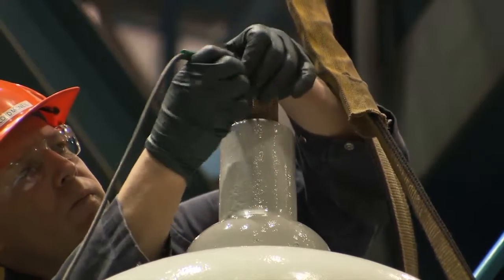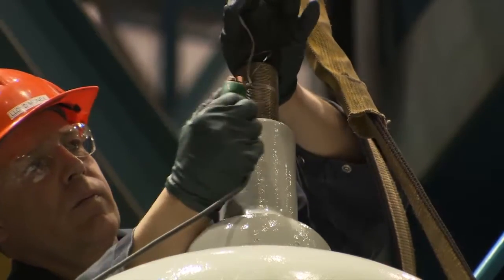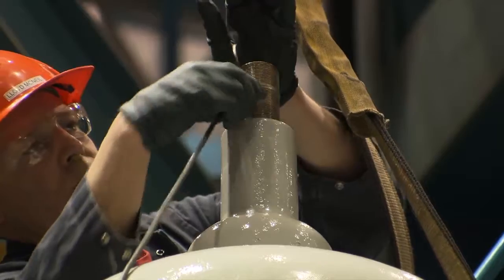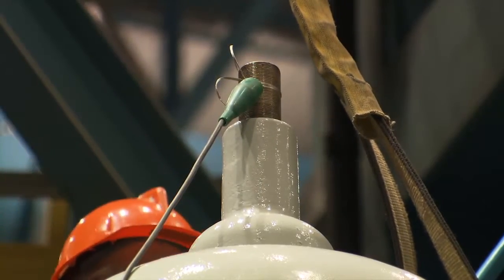To conduct the Megger test, the extended cable for the voltage lead can be connected to the conductor core via the threaded rod extending out from the top of the terminal at the top of the bushing.